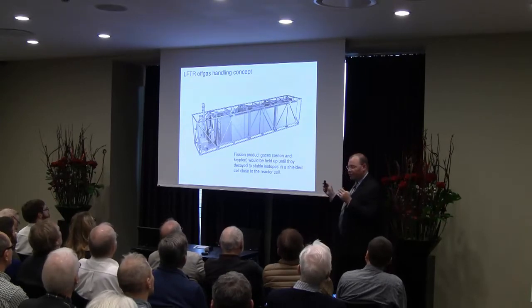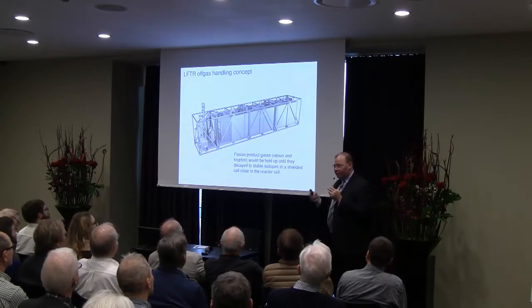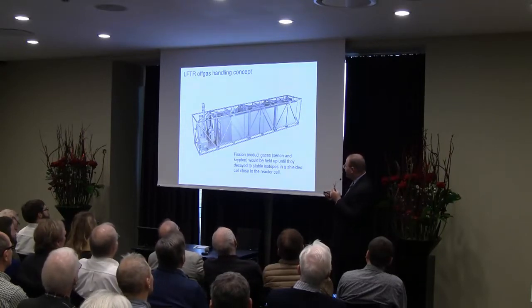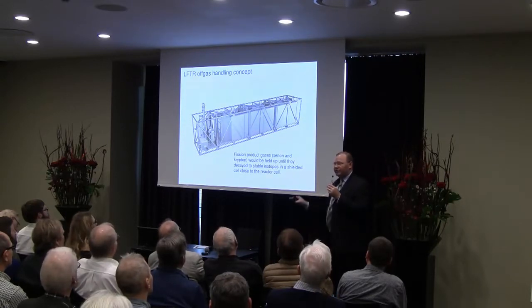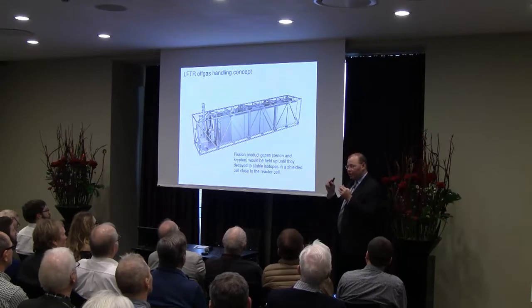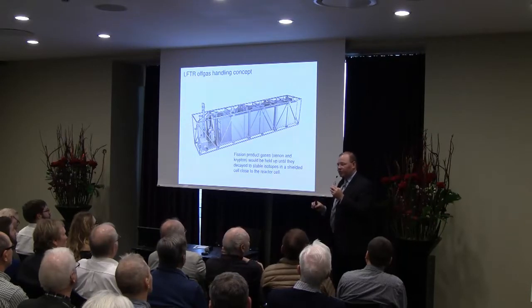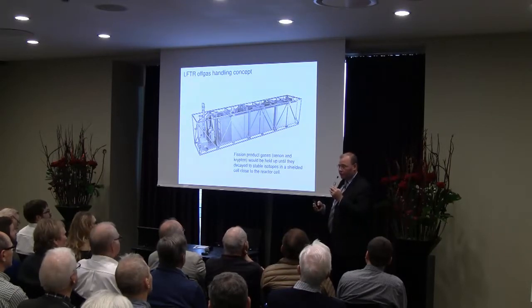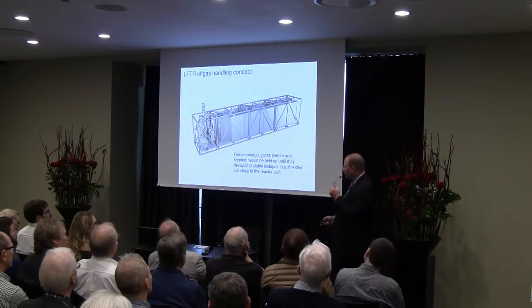The off-gas is another part of it — the xenon and krypton that come out of solution allow the reactor to load follow safely. These are shunted to a system where they decay away over a period of about 45 days. All the xenon decays to stability in about a month, and everything in the krypton except krypton-85 decays away. The krypton-85 can be isolated and potentially sold to those who could use radioactive krypton, while the xenon stream is completely stabilized.